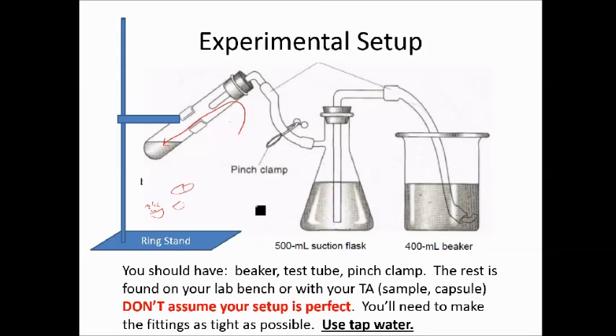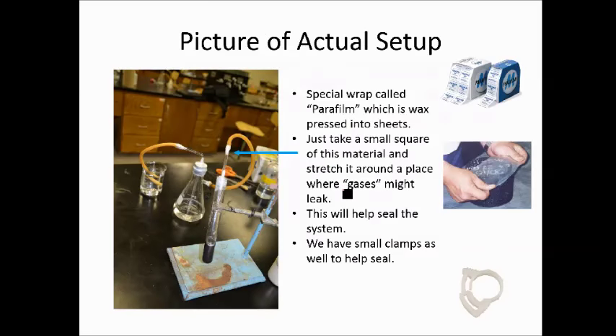Now there may be some things that are set up there, but don't assume it's set up. We want everything to be airtight, like every connection we want to be airtight, because you're going to have hydrogen. You look at every connection and you think about where hydrogen can get lost there today. Use tap water in here. Follow the procedure to get this filled up properly and set up.